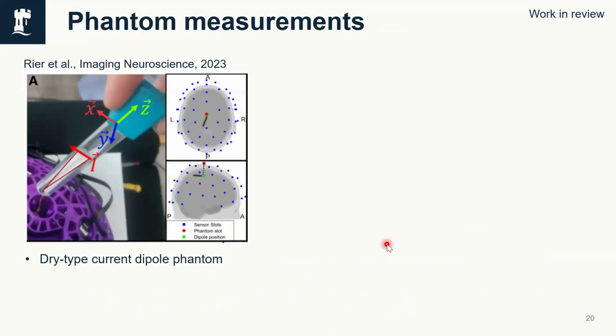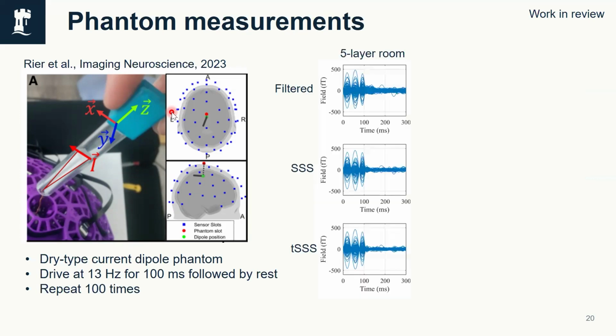We tried this first with a phantom. So we have a sort of triangular dry phantom, so it generates a sort of current dipole measurement. We drove it at about 13 hertz to simulate a sort of evoked response experiment and averaged over a lot of trials. And this is our results in our 5-layer room. So regardless of what we do, if we filter the data, we see the nice signal. If we do SSS, we see the nice signal. We're not distorting the temporal form of the signal. And if we do TSSS again, we see the nice signal.